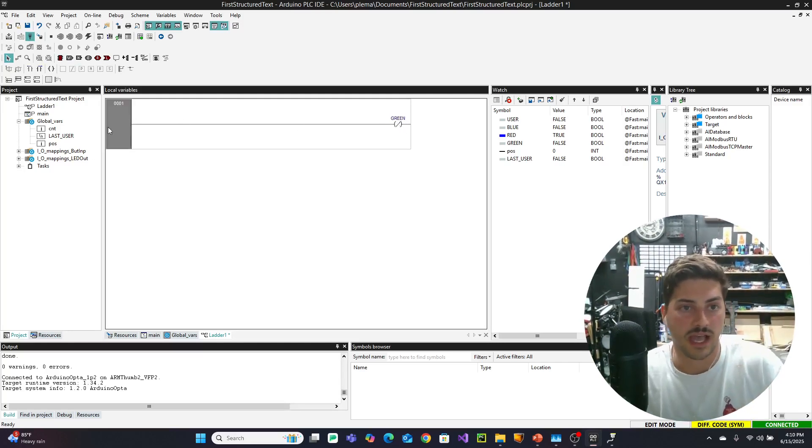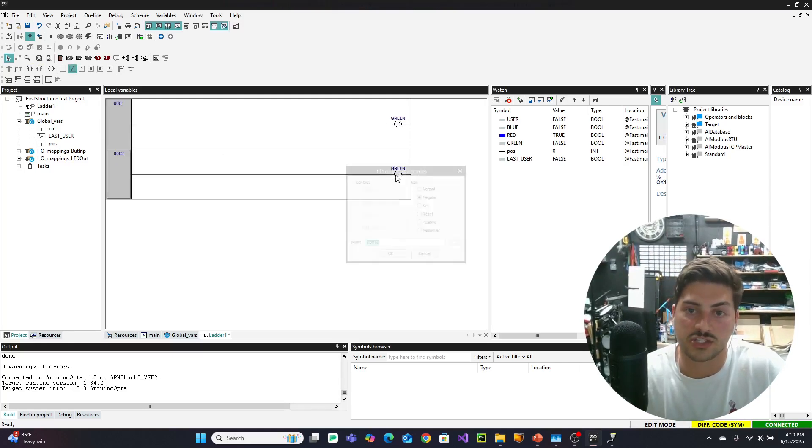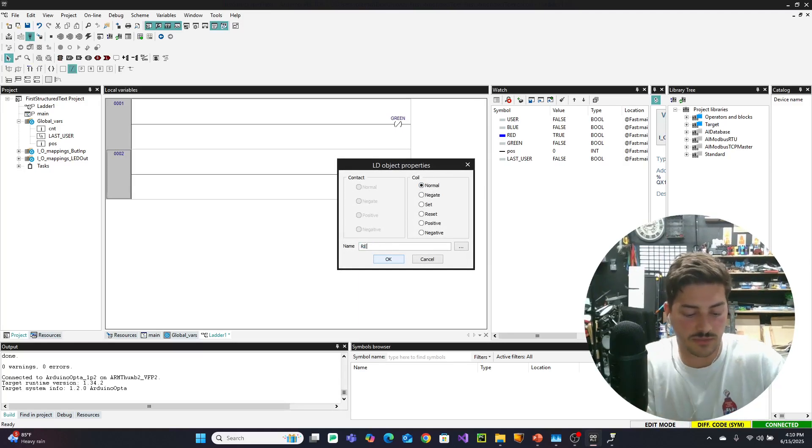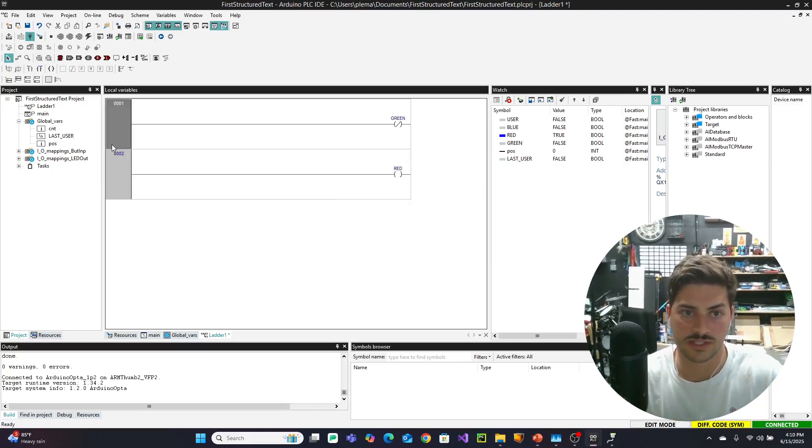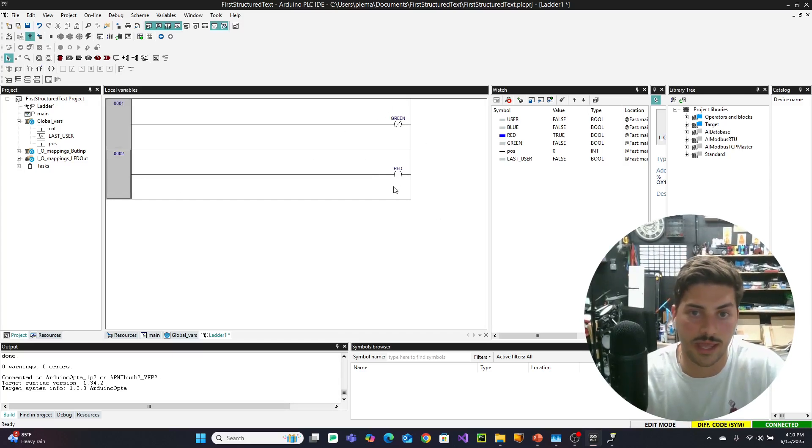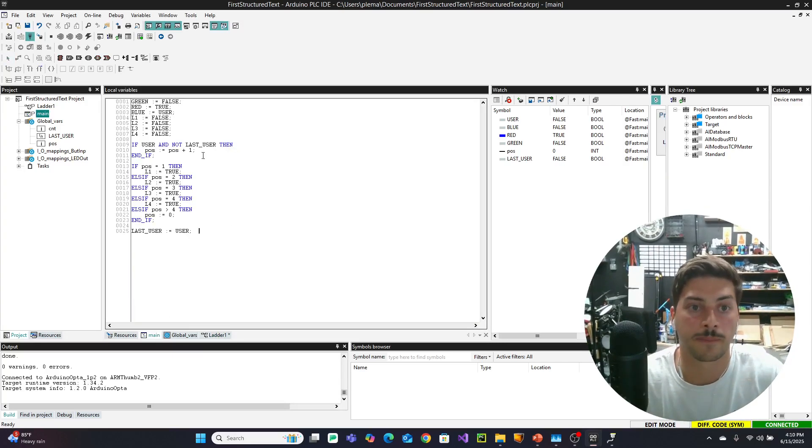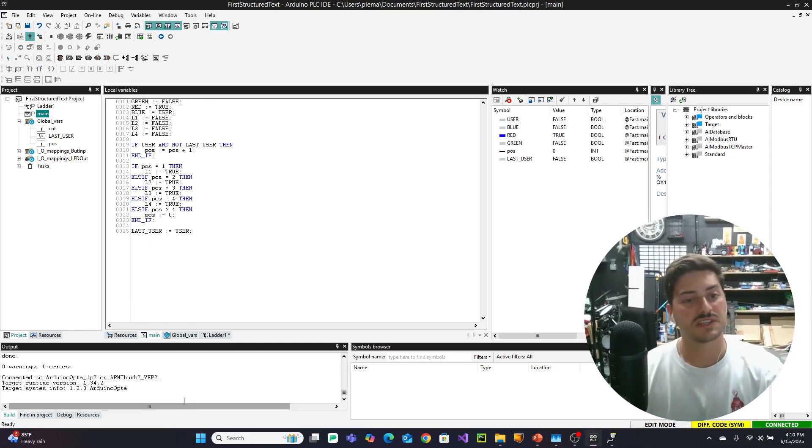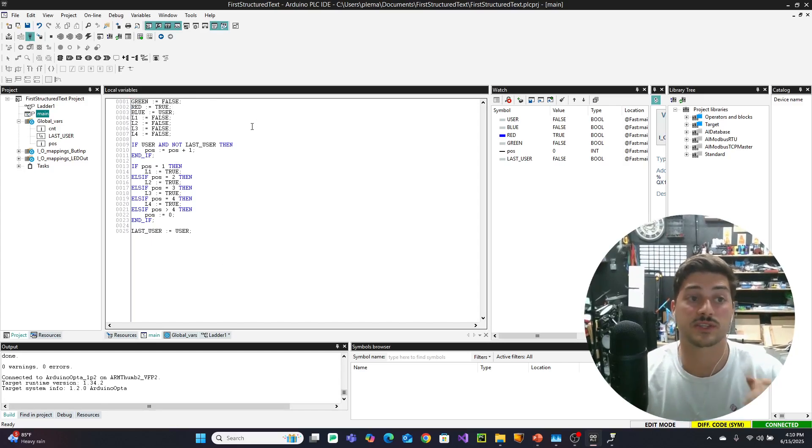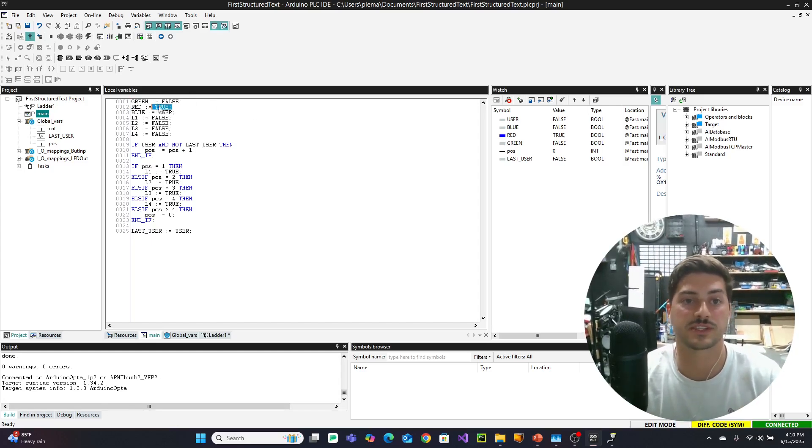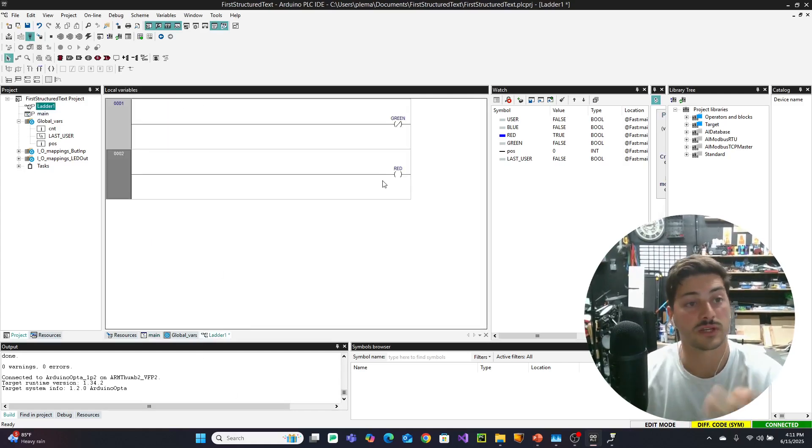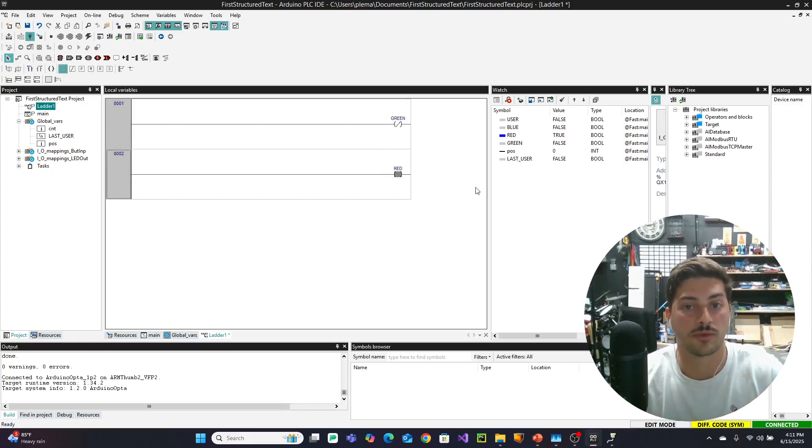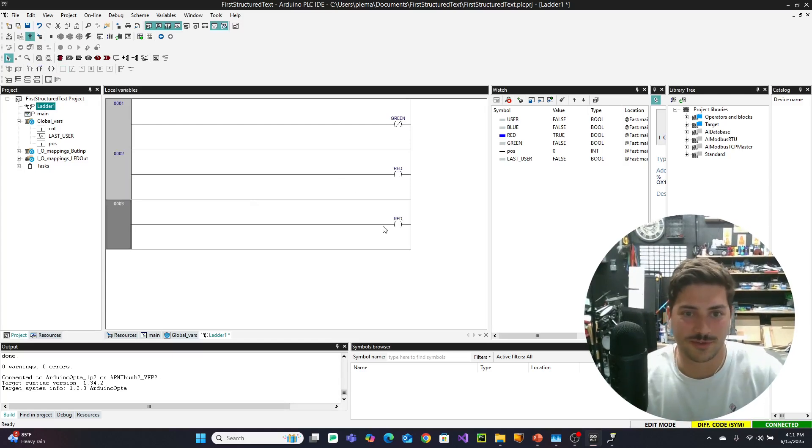So it's basically green is not on. If I copy this whole ladder one, and I change this to normal, and I change this name to red, this line of code reads as red is always on. So we have green, always false, red, always true. That's what line one and line two here are doing. And it looks like this in structured text. Green is false, red is true. So you can see right away, just with this basic comparison, that ladder is a super visual language. There's nothing that explicitly tells you it's true or false. It's telling you, based on what relays in electrical schematics look like, that green will not be true, and red will always be true.